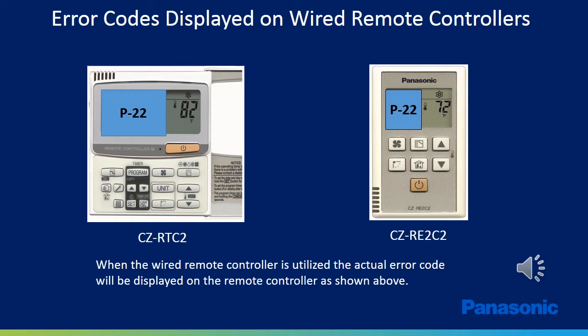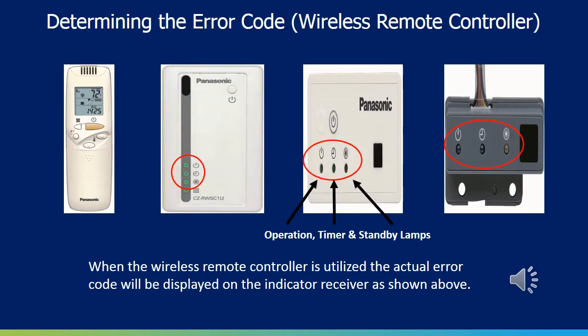The wired remote controller also allows access to the indoor unit's main control board to view items such as alarm history, monitor temperatures, and be able to make changes to the factory program settings on the indoor unit. When utilizing the wireless remote controller, when an error code occurs, it will be displayed on the indicator receiver lamp assembly as shown in this slide.